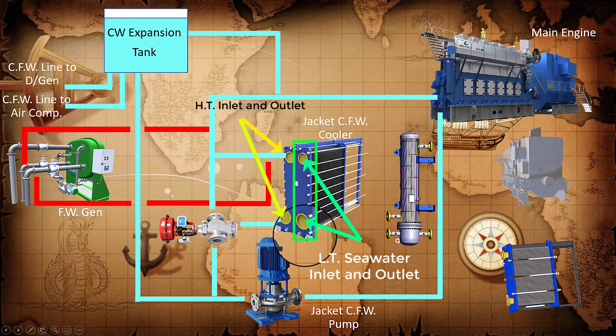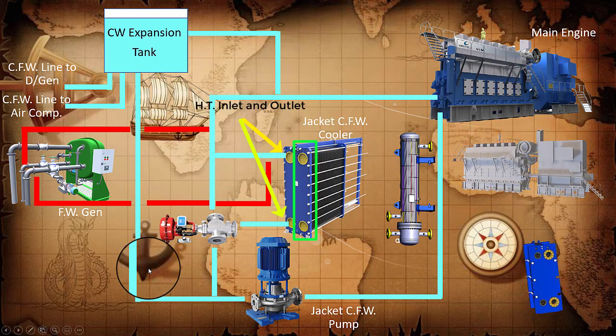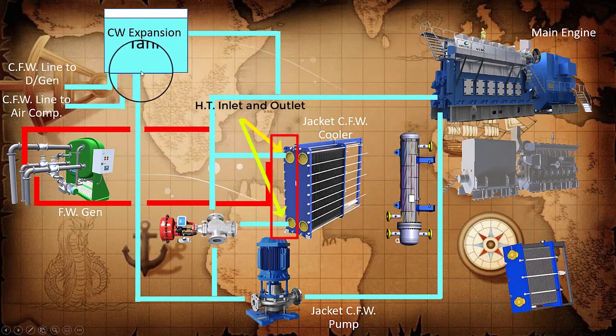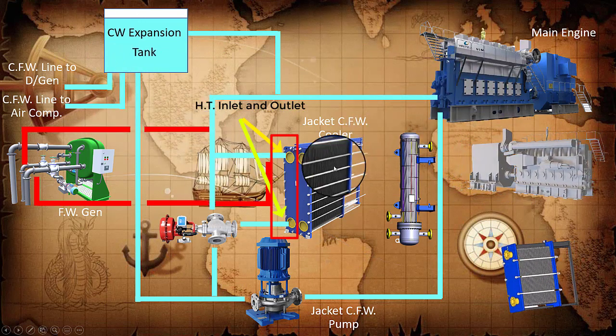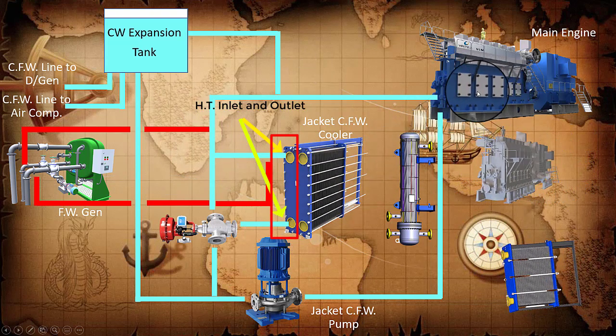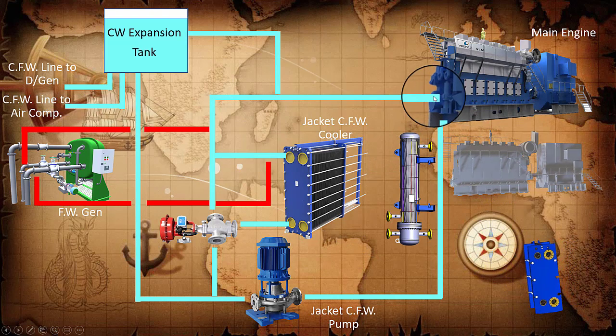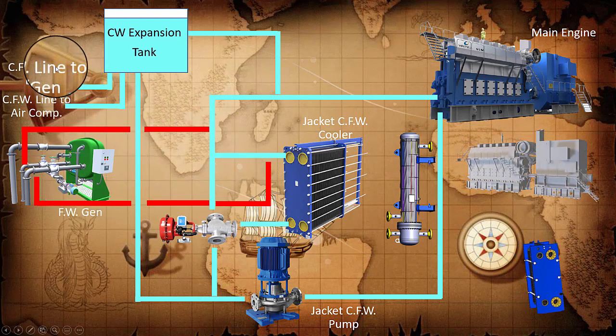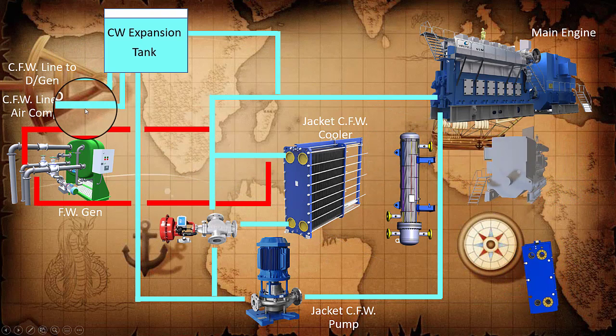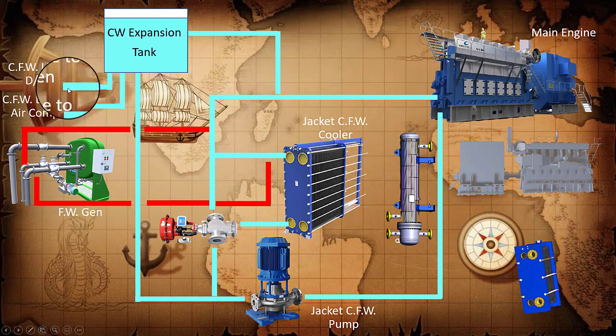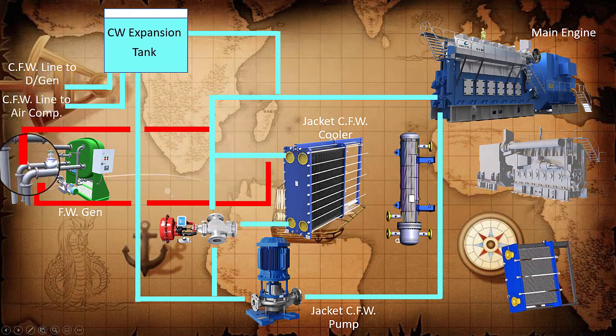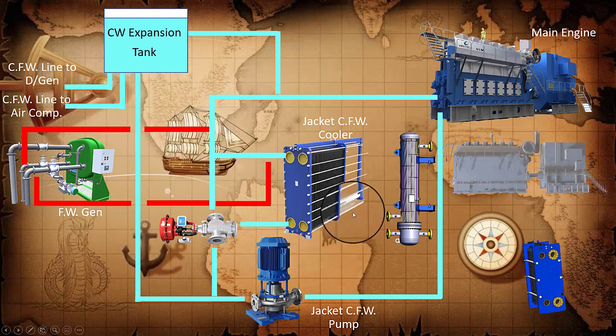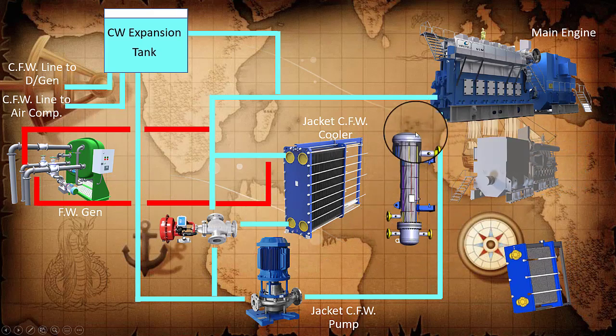The temperature of the low temperature circuit is lower than that of the high temperature circuit. The high temperature circuit in the central cooling system comprises the jacket water system of the main engine, where the temperature is quite high — about 80 to 95 degrees, depending on the engine and system. This is also used for the fresh water generator and diesel generator during standby condition, and they are circulated through electrical cooling water pumps. When the main engine is stopped, it has to be kept warm by high temperature cooling water from the diesel generator. If the diesel generator is not sufficient regarding temperature, then a heating medium is also utilized, in this case a steam-heated fresh water heater.